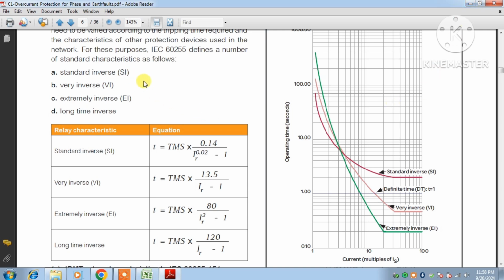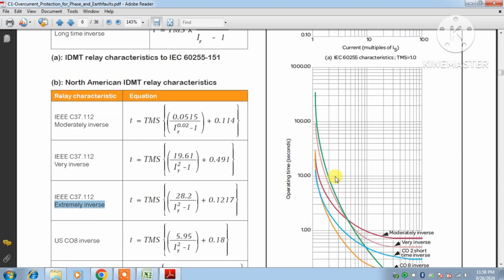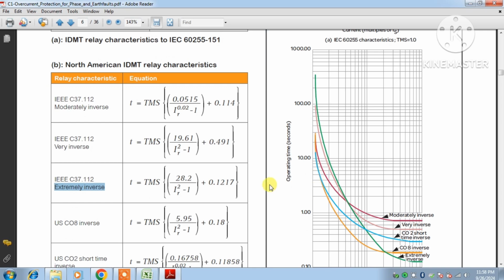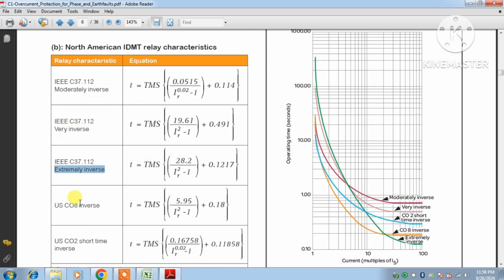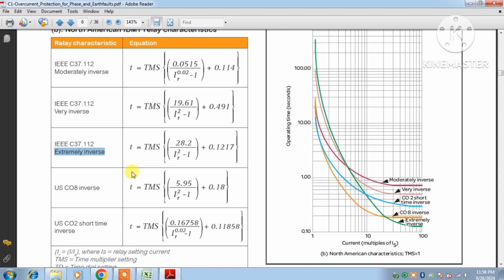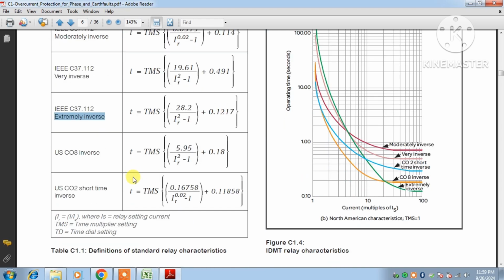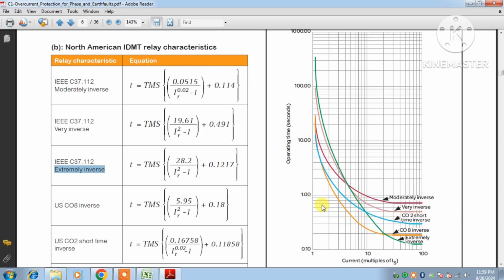This is the IEC standard. It follows the 60255 standard, and it has very inverse, extremely inverse and standard inverse curves. So these are the curves. It has inverse definite minimum time: the higher the current, the less the time, and the lower the current, the higher the operating time. This is the characteristic. One more category is the IEEE, the Institute of Electrical and Electronics Engineers. Accordingly, there are moderately inverse, very inverse and extremely inverse types of curves. C08 and C02 standards are also there, which are followed in the US. These are the different curve parameters, and this is the current versus operating time curve.